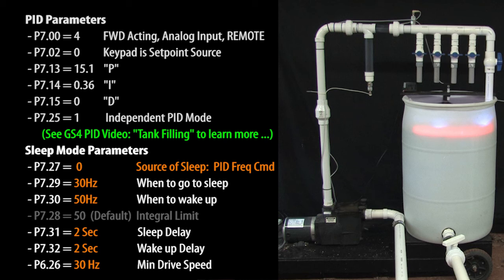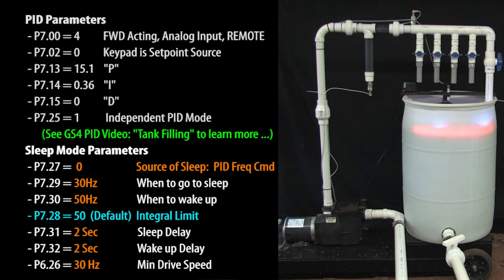The good news is the GS4 drive has this integral limit parameter where you can specify a limit for the max duration of the integral term. That way you can control how quickly the process recovers after the motor has been off for a while.